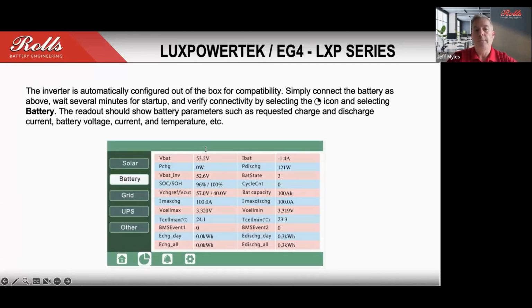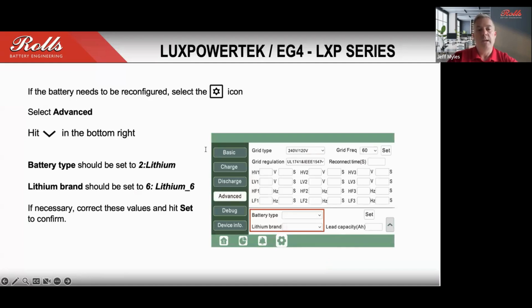So going through the inverter setup, we've walked through essentially the setup of a stack, and what battery selection would be set. With these particular units, you're going to have a voltage range that you can set, much like a traditional deep cycle battery, depending on the conditions you may or may not have. But we've walked through the setup through the menus on those particular models to give you an indication of what should be set to be compatible with a stack, whether it's 1 unit or up to 8 units. So throughout this manual, the documentation is going to provide you the screenshots.